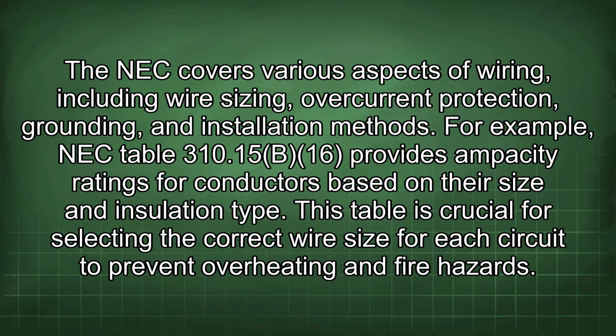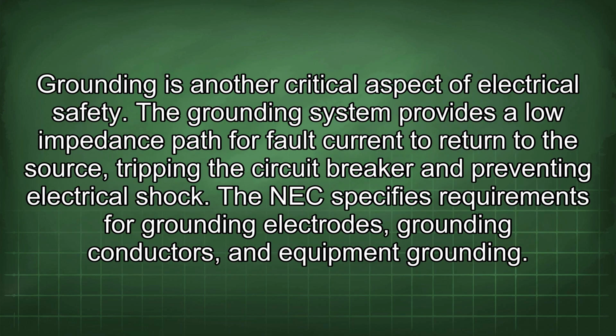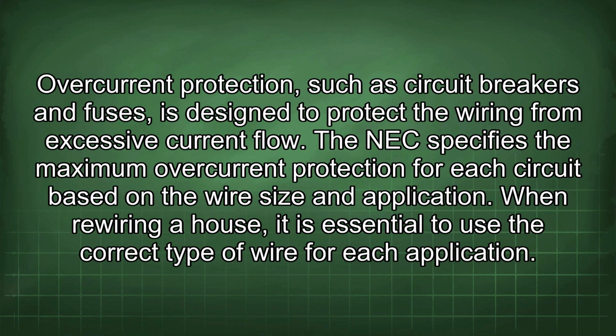For example, NEC Table 310.15(B)(16) provides ampacity ratings for conductors based on their size and insulation type. This table is crucial for selecting the correct wire size for each circuit to prevent overheating and fire hazards. Grounding is another critical aspect of electrical safety. The grounding system provides a low impedance path for fault current to return to the source, tripping the circuit breaker and preventing electrical shock. The NEC specifies requirements for grounding electrodes, grounding conductors, and equipment grounding. Overcurrent protection, such as circuit breakers and fuses, is designed to protect the wiring from excessive current flow. The NEC specifies the maximum overcurrent protection for each circuit based on the wire size and application.